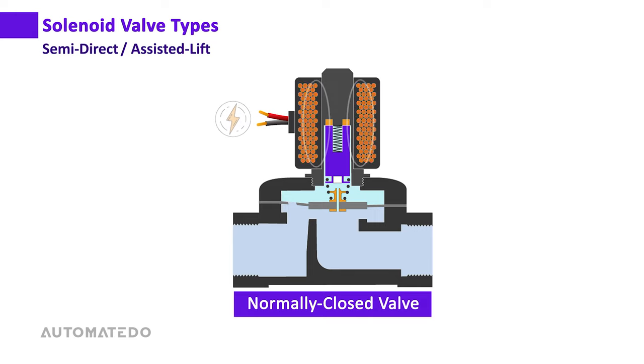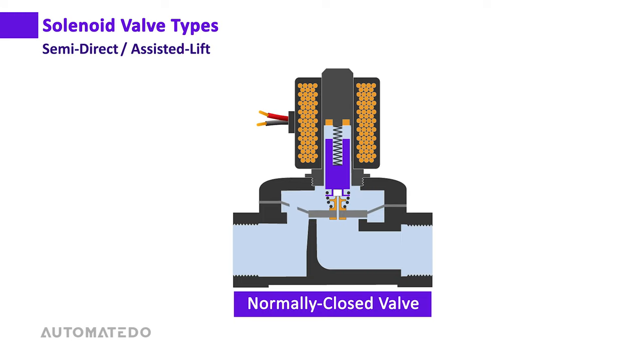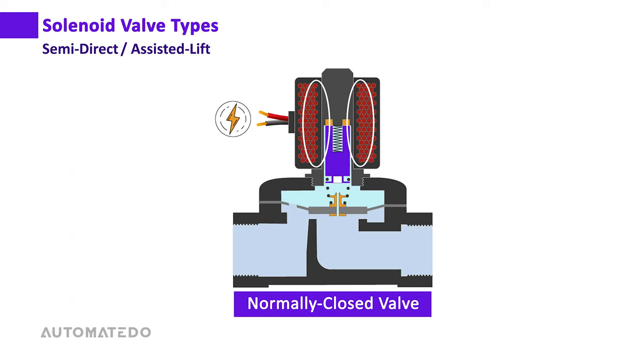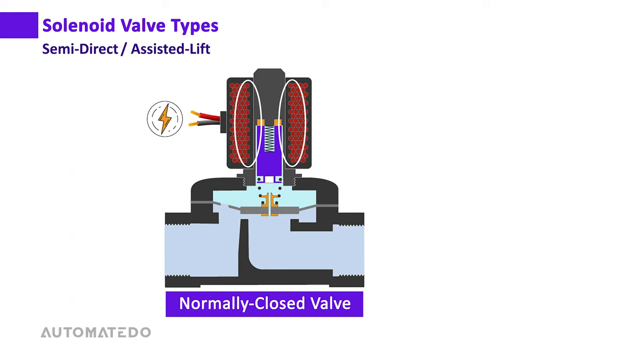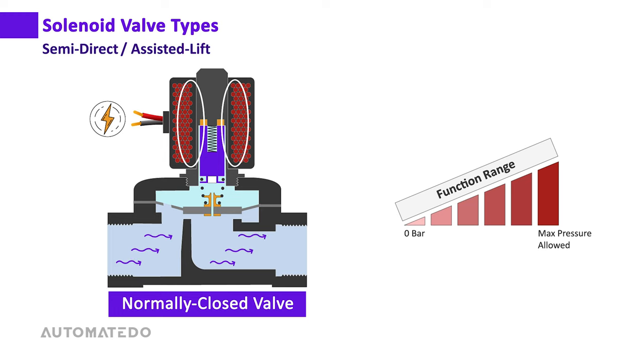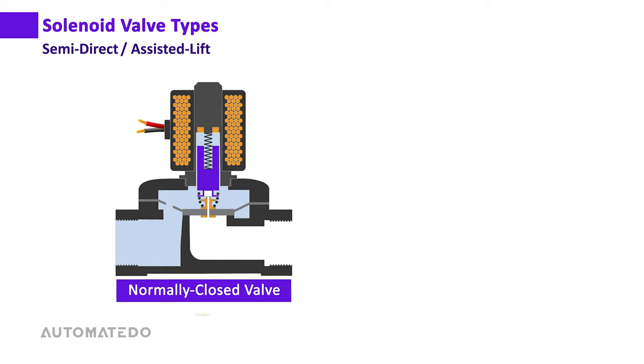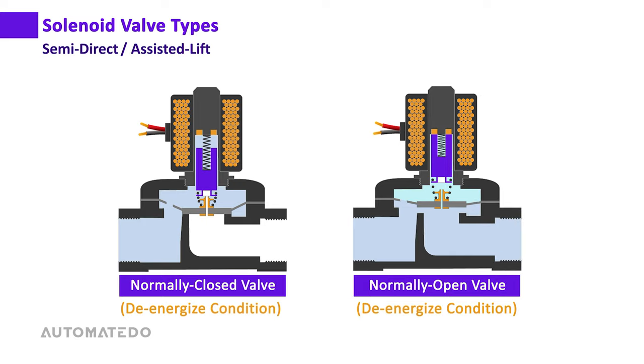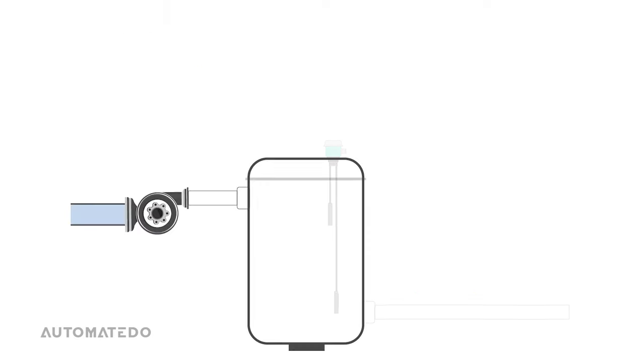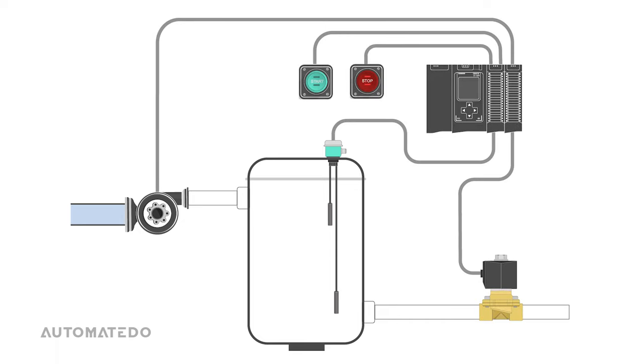As soon as the solenoid is de-energized, the plunger falls, lowering the diaphragm and closing the orifice, which increases pressure above the diaphragm and shuts the valve. The semi-direct acting solenoid valve can operate from zero bar and controls high flow rates. The normally open valve operates on the opposite principle.